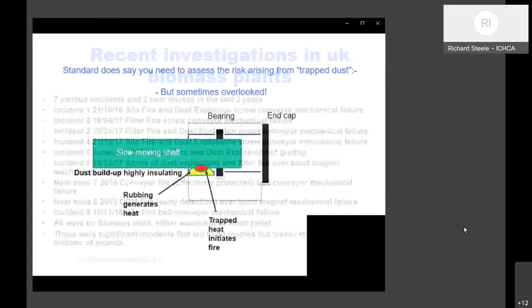And one of the challenges is that people don't always read the standards properly. For example, one of the common causes of ignition is where you get dust trapped in an area where there is moving equipment. For example, between the shaft and bearing housing, if you get dust packed in there, it rubs, it can get hot, and then that can start to smolder and can initiate a fire or an explosion.